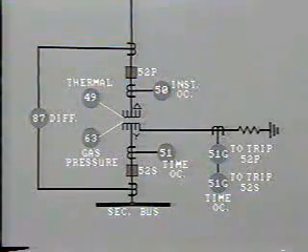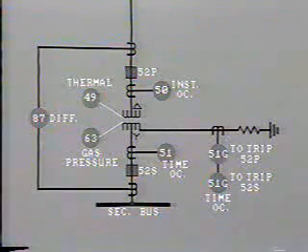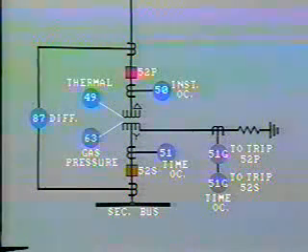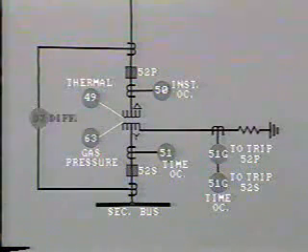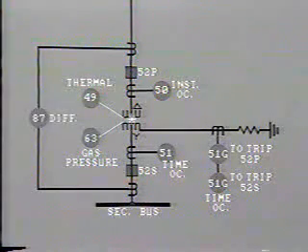But as you probably know from experience, you soon get accustomed to certain numbers, especially those referring to protective devices. Every time you look at a schematic and see the number 87, you know that this refers to a differential protection relay. In this case, differential protection across the primary and secondary of a transformer.